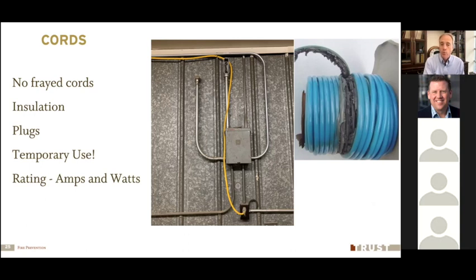If you try to draw more than 1200 watts through that cord, it may not trip the breaker, because it's a 15 amp breaker. It's probably going to take 1800 watts to trip that breaker. But if you're trying to run more than 1200 watts through that 10 amp cord, the cord could get hot and melt, and it could cause a fire. So be really careful with temporary wiring and extension cords. Make sure they're up to the task you're using them for, especially retractable cords that roll up onto a reel. The extra heat generated inside there could cause that whole coil of wire to melt if you're drawing too much power through it.